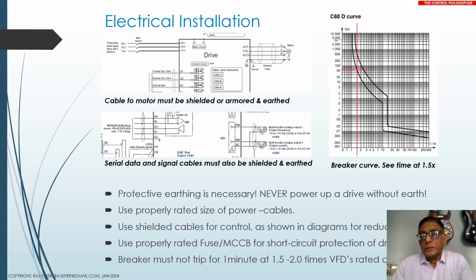Now, as I said earlier, the breaker should not trip for at least 1 minute at one and a half or two times the VFD's rated current. Now, the time between one and a half and two multiples is not all that significant because we are well within the short circuit protection requirements. Okay, short circuit currents are always much higher than one and a half or two times. That one and a half to two multiple is just to take care of starting surges.